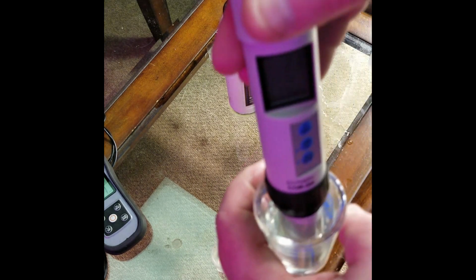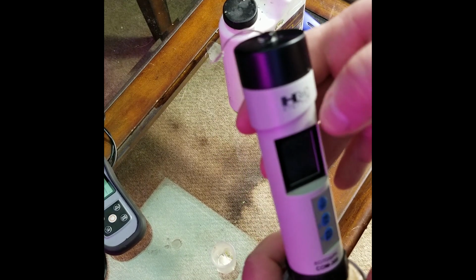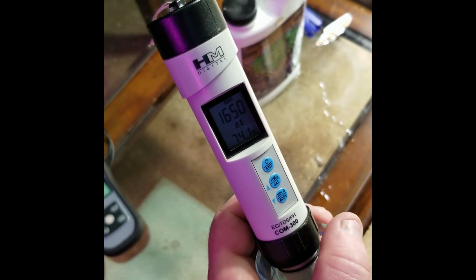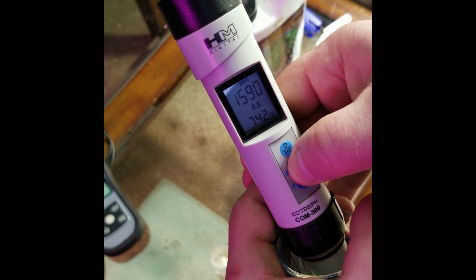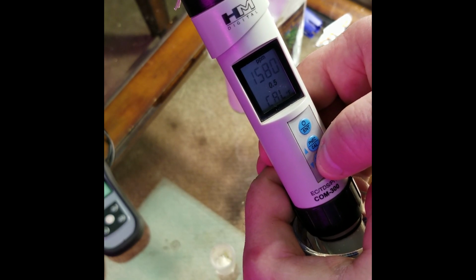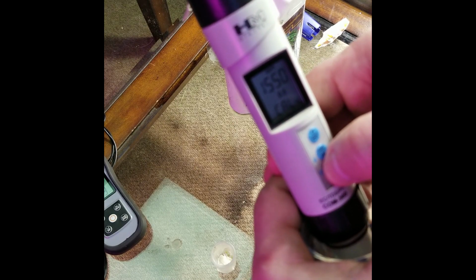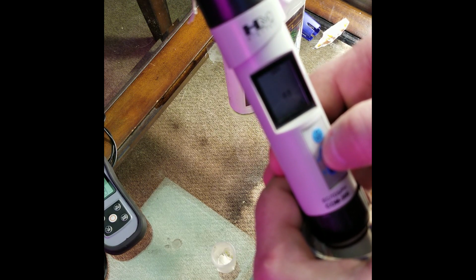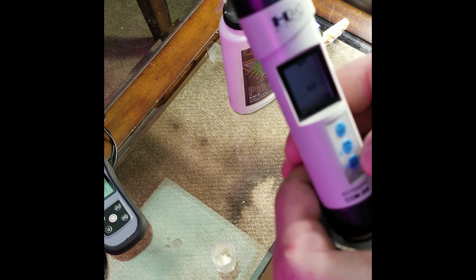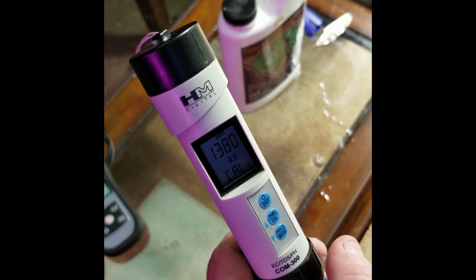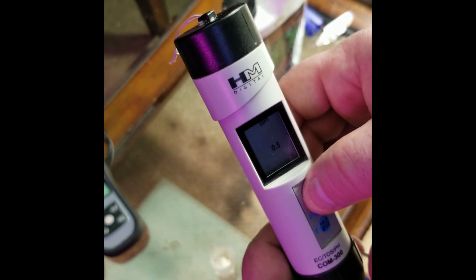And again, this meter is a little different. So we're going to put it in the solution. See if I can do this like this. Now this one reads 1660. Yeah, there we go. A little bit better. 1660.5. We're going to press and hold calibration. It's going to flash. We're going to down arrow until we get our, we went too far, until we get our 1380. I'll go lower than upper, so 1380 is now flashing. I believe I have to hit my enter key.